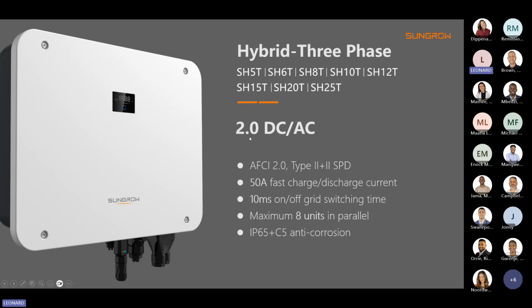And we have a 200% DC-AC ratio. So you can actually add 200% of the inverter's capacity in terms of DC capacity. So with the 25T, you can actually add 50 kilowatts of PV to it, and then you can charge your battery with 25 kilowatts and supply your AC loads with 25 kilowatts at the same time. So essentially, it has a 50 kilowatt MPPT rating, and the same with the 15T, which is a 30 kilowatt MPPT rating.